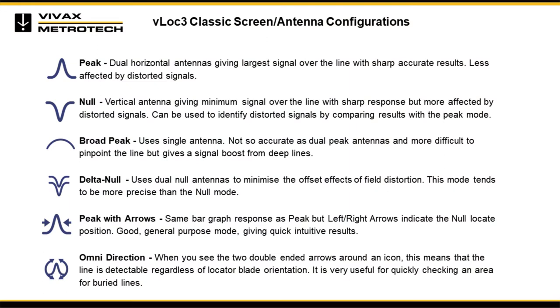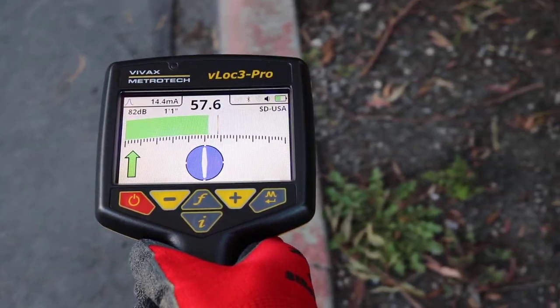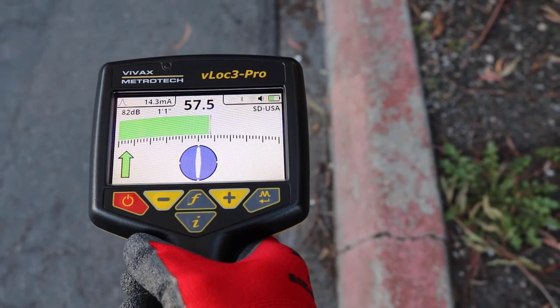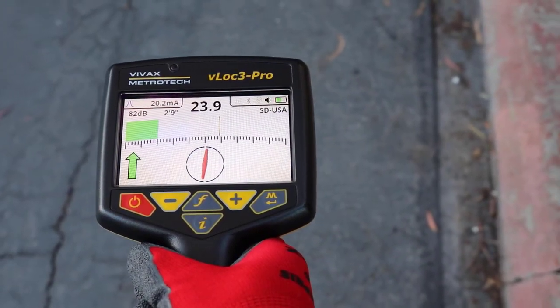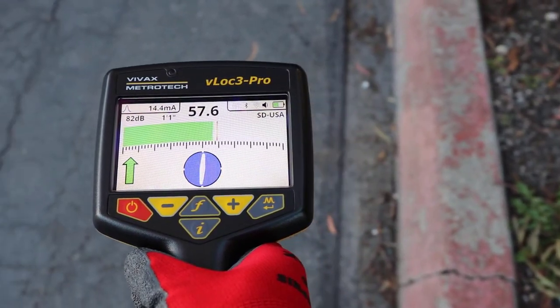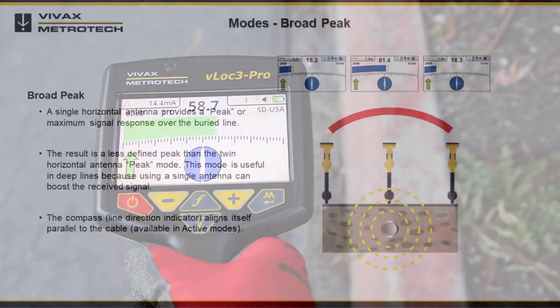The vLoc3 series receivers have an array of six antennas that can be toggled through different configuration modes by pressing the M key. Peak mode uses two horizontal antennas to provide a peak or maximum signal response over the buried line. It is an accurate locating method as both antennas provide a clearly identifiable peak, and it is less prone to signal distortion effects. The peak level indicator on the bar graph marks the largest signal detected, and the compass line direction indicator aligns itself parallel to the cable in active modes.